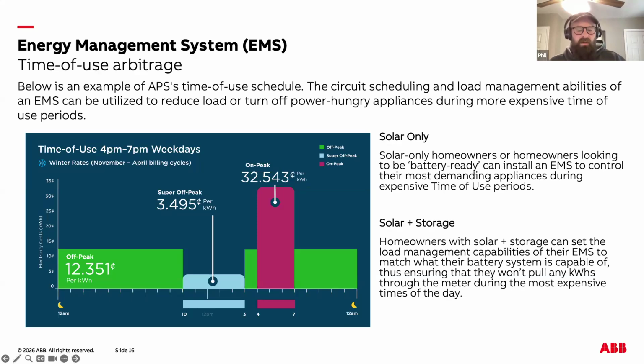Customers with solar only can install an EMS to control their most demanding appliances during the time of use window to reduce load or turn off appliances altogether to provide cost savings. If the EMS that's installed can also provide PCS functionality, then the customer will be battery ready for a whole home backup. Folks that already have a solar and storage system can set the EMS PCS set point to match what their battery system is capable of, thus ensuring that they don't pull any erroneous kWh through the meter during the most expensive time of the day.